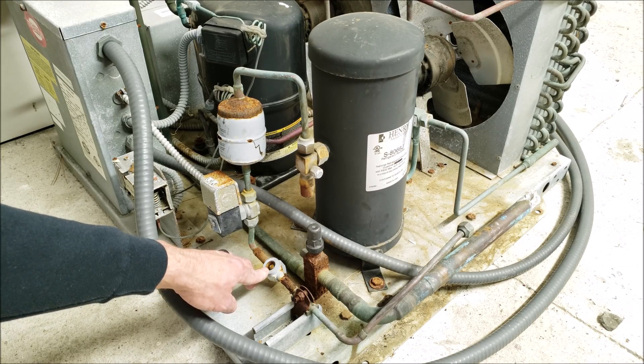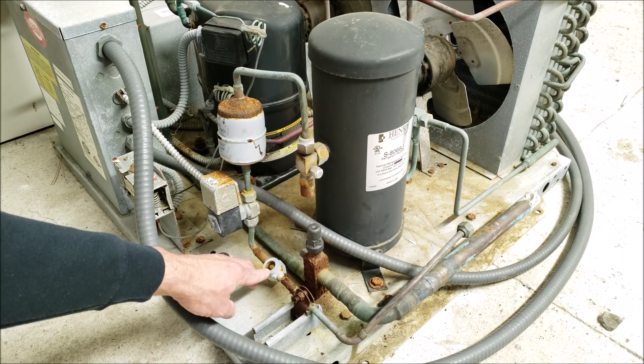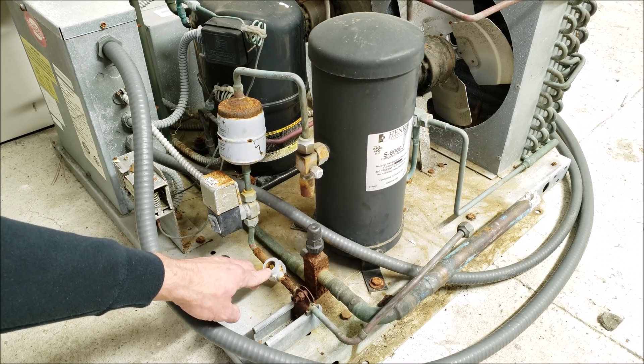If the sight glass is right before the thermostatic expansion valve, you'd be able to tell that you're not losing subcooling before reaching the TXV. You want to make sure that you have a full liquid flow to the TXV in order for the metering device to operate correctly.